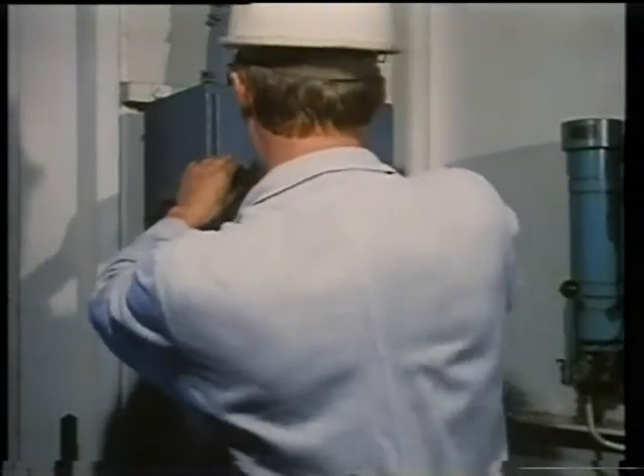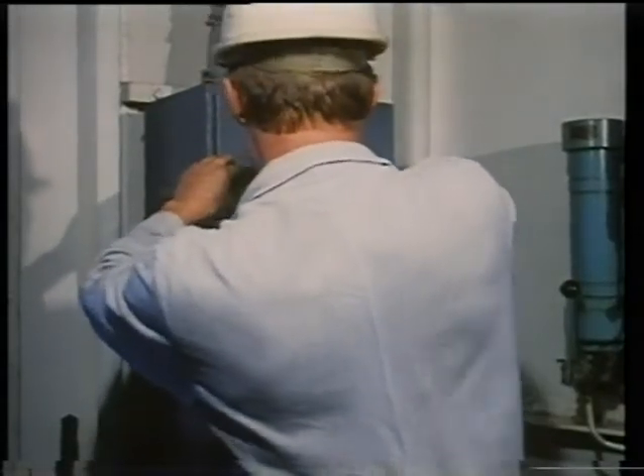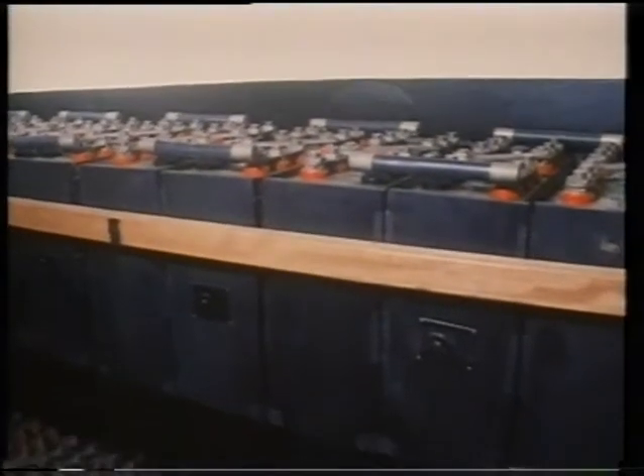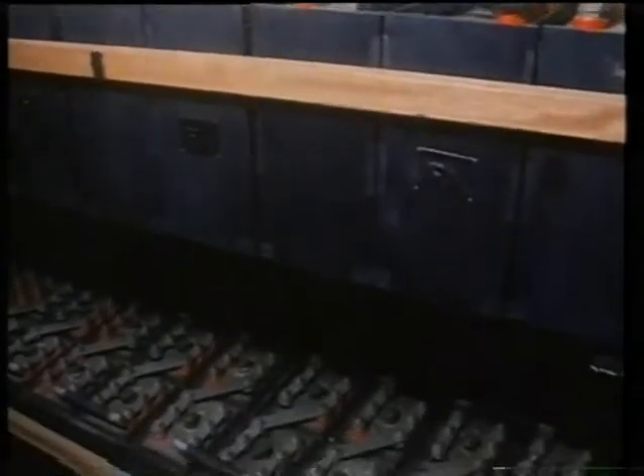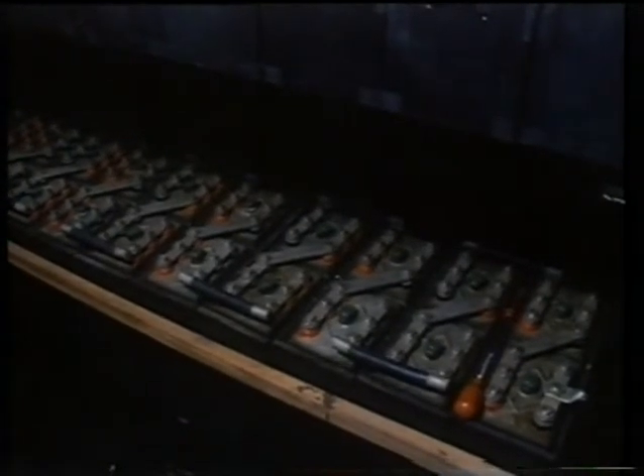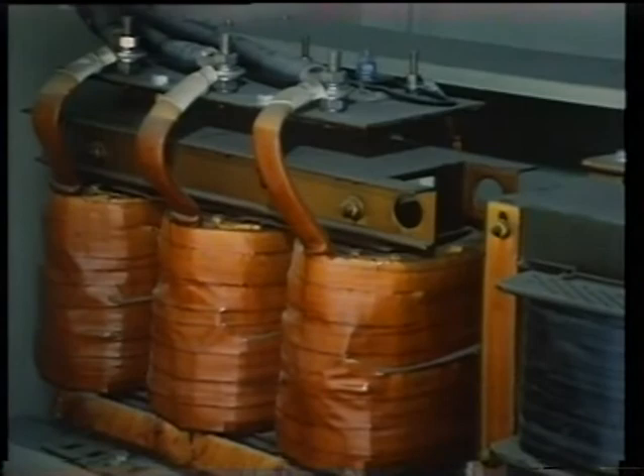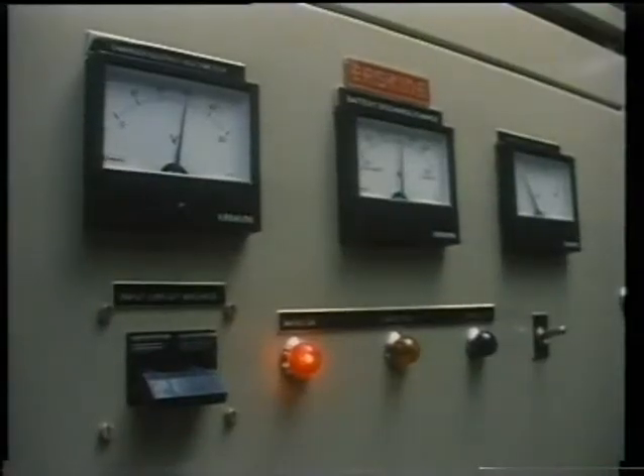The shore connection box is normally fitted with a voltmeter and a phase sequence indicator. In addition to this, a minimum level of lighting, fire and general alarms and communication systems must be supplied by a battery supply during an emergency, when the main supply is interrupted for any reason. In normal conditions, this supply is provided by a separate transformer rectifier system, and the batteries are on charge from a battery charger. Alternators are described in greater detail in Programme 3, and a more thorough description will be found in the book forming part of this series.